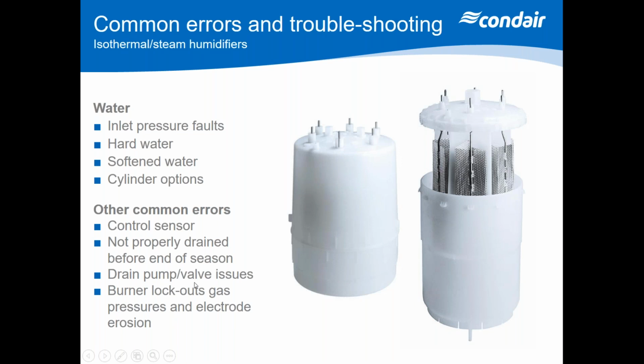Another factor I see an awful lot of is that the humidifier probably runs through the winter period and then turns off for the summer. Ideally, you want to drain those cylinders down at the end of the season before they start the season again in September, because if you leave them in water, those electrodes are going to rust, and then you get the mild steel exposed, and then all of a sudden, oh look, we've got a problem now with the unit not working at the start of the season. Drain pump and valve issues, as I mentioned, is very important to make sure they're draining and diluting correctly.